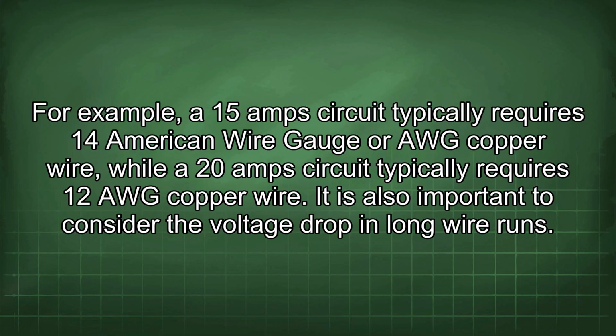For example, a 15 amp circuit typically requires 14 American wire gauge, or AWG, copper wire, while a 20 amp circuit typically requires 12 AWG copper wire. It is also important to consider the voltage drop in long wire runs.